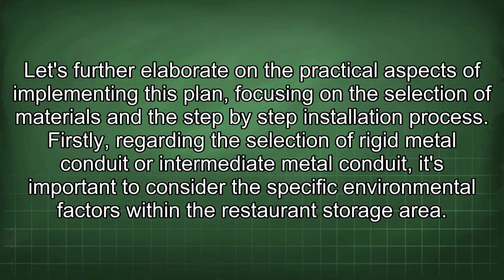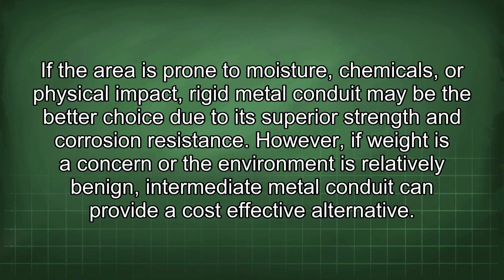Let's further elaborate on the practical aspects of implementing this plan, focusing on the selection of materials and the step-by-step installation process. Firstly, regarding the selection of rigid metal conduit or intermediate metal conduit, it's important to consider the specific environmental factors within the restaurant storage area. If the area is prone to moisture, chemicals, or physical impact, rigid metal conduit may be the better choice due to its superior strength and corrosion resistance. However, if weight is a concern or the environment is relatively benign, intermediate metal conduit can provide a cost-effective alternative.